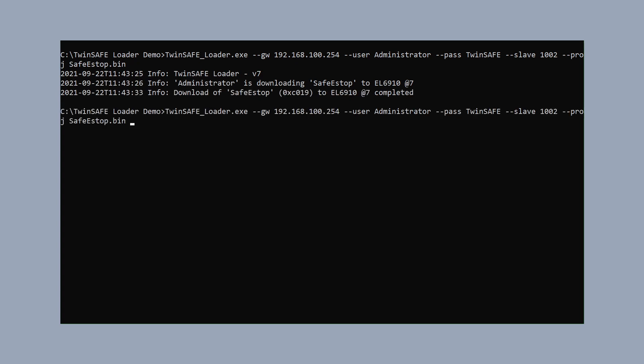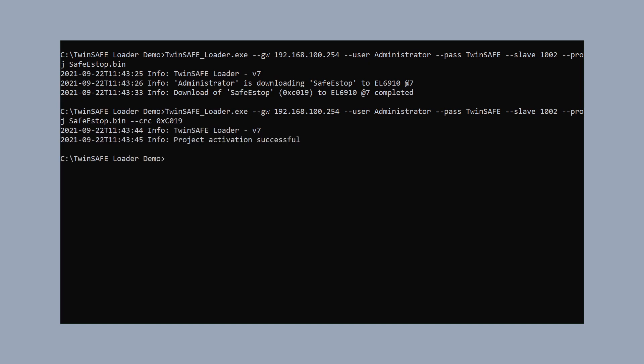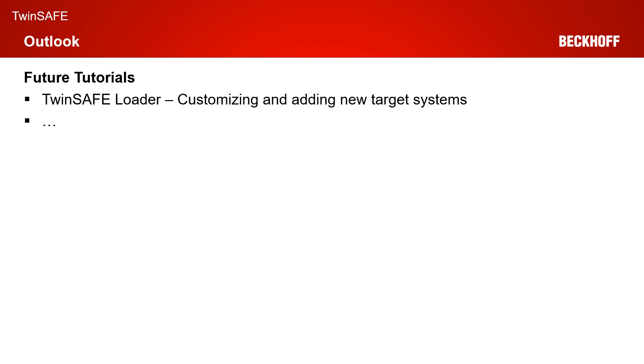When the download is completed, we use the same call as before with an additional parameter 'crc' and our CRC value C019 to do the activation process. After that command finishes, we have downloaded and activated the safety project. We could now activate the configuration and use our safety project as if we had downloaded it via the TwinCAT 3 download button. That was all for the live demonstration today.